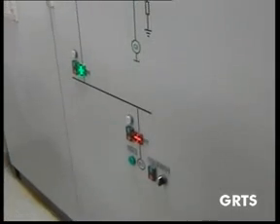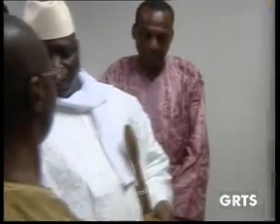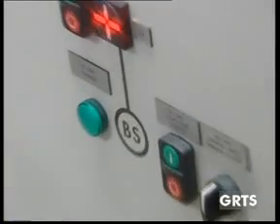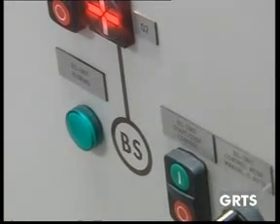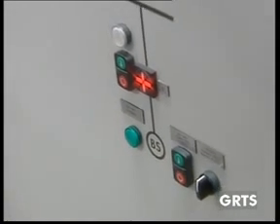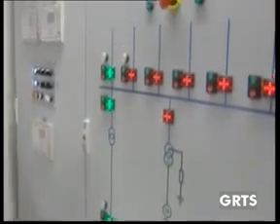Now, I've seen automatic shut-off in case something is wrong. Do you have a backup system, so that if it goes off all of a sudden there is no blackout for the office here? Yes, this is why we have a smaller generator, a black start generator, which is also connected. Once the voltage is lost, it starts automatically to feed our auxiliaries, and then we can work on the conditions.